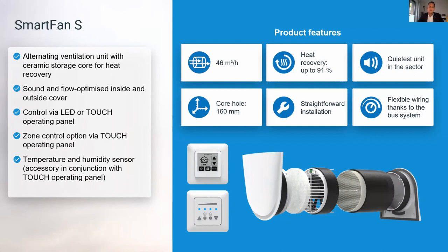We can achieve up to 91% heat recovery, and in the summer months, also the opposite way around, giving you a little bit of cooling. It's also very easy to install because we have a bus system installed, which allows for flexible wiring. This means you don't need to connect each fan to the control unit and then to the next one. You can go in serial or in row installation, for example.